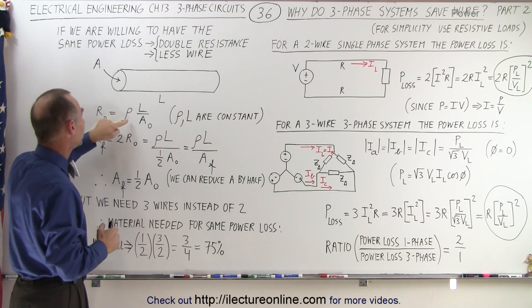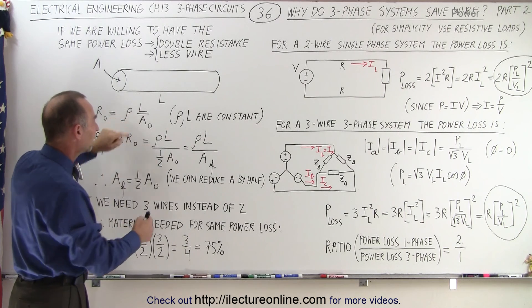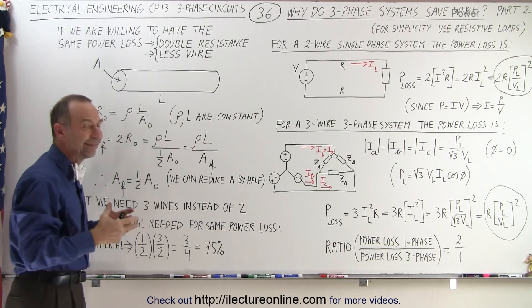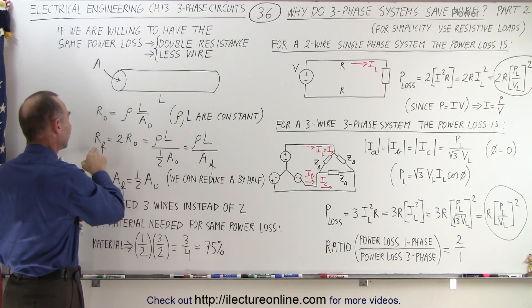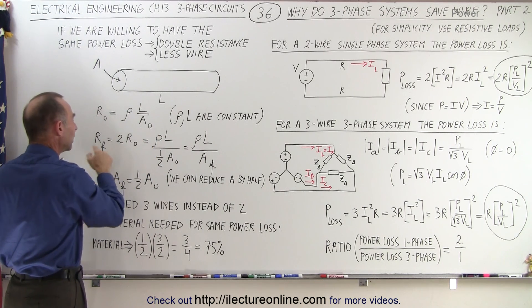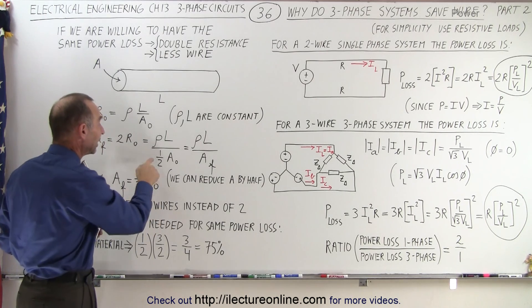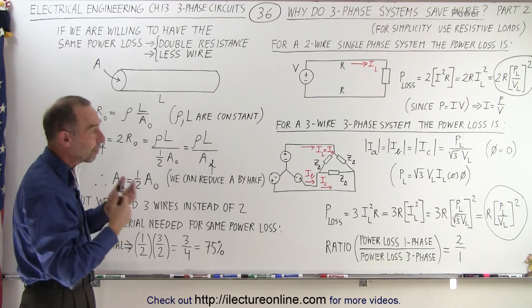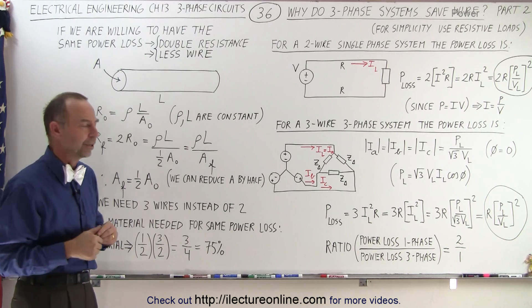Since the resistance is equal to the resistivity times the length divided by the cross-sectional area, and realizing that the resistivity and the length are the same for both systems, we can only change the cross-sectional area. Therefore, if the final resistance can now have twice the resistance, we can get by with half the cross-sectional area. In a three-phase system with the same power loss, we can go to half the cross-sectional area.